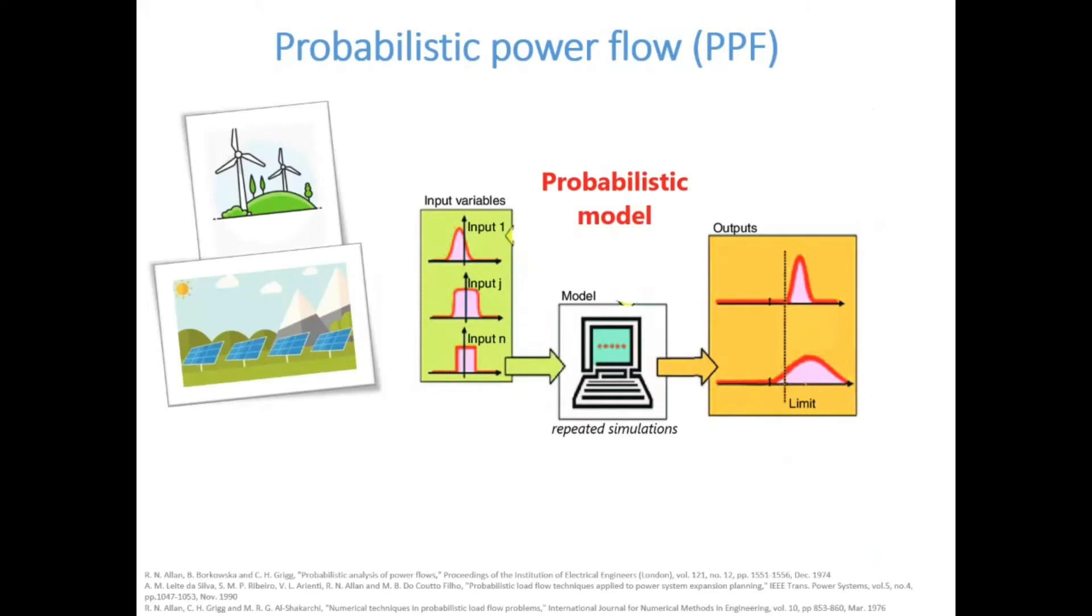These uncertainties can be effectively modeled using a probabilistic power flow. The probabilistic power flow was first proposed in 1974 and has been further developed and applied in power system operation and planning. The probabilistic power flow requires inputs with probability distribution functions to obtain bus voltages and power flows in terms of probability distribution functions so that the system uncertainties can be included and reflected in the solution.